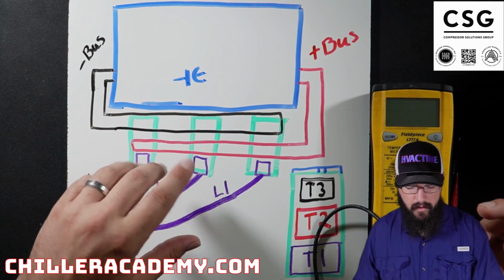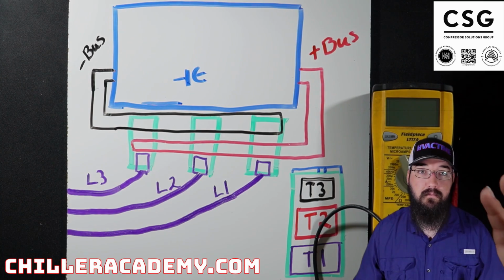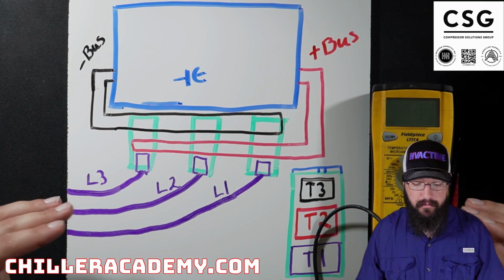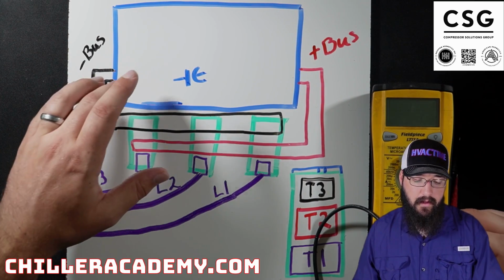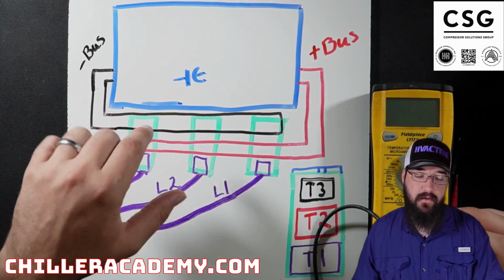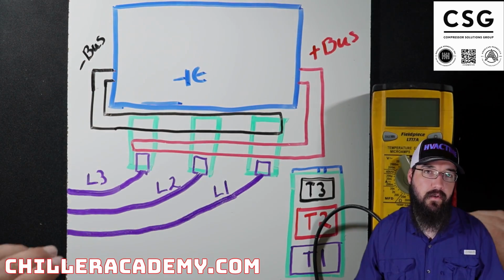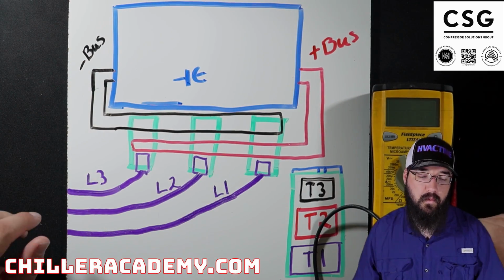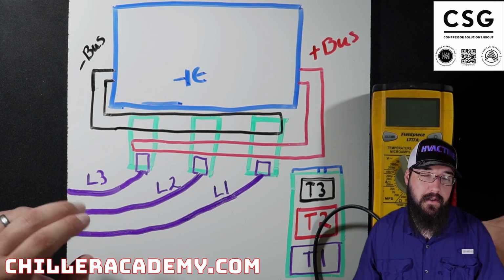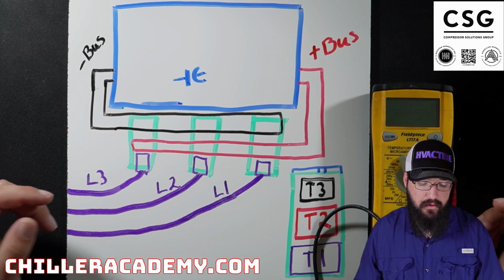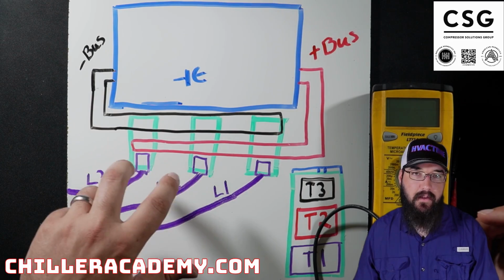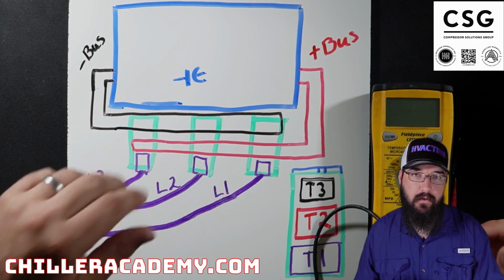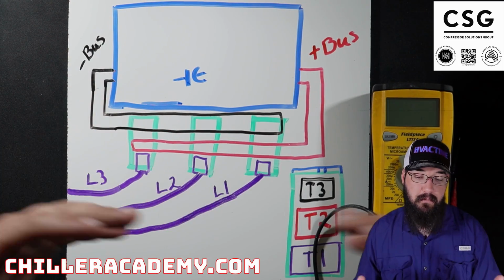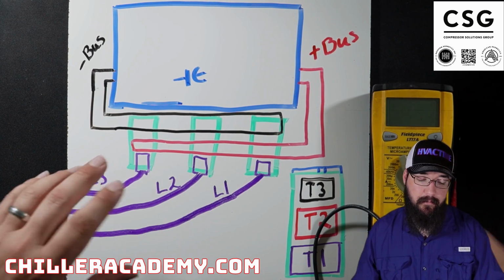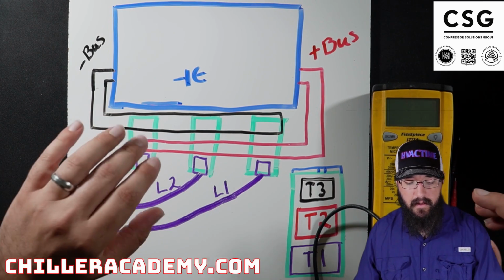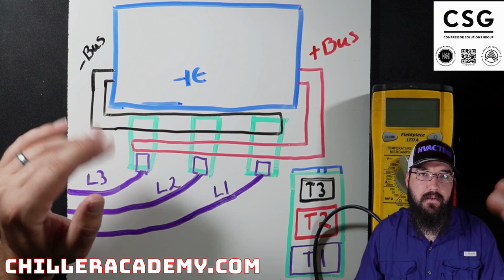I've opened it up, and I had two SCRs that quite literally just exploded. They're in a few different pieces. And then drilling into the drive assembly, I'll find that one or two of the capacitors also swole up. Which one took out the other? Who's to say? Not really sure. More than likely, it's the SCR shorting across, overloading the DC bus, and also mixing that AC and DC together, which caused a big bang, and the capacitors got taken out in the process.